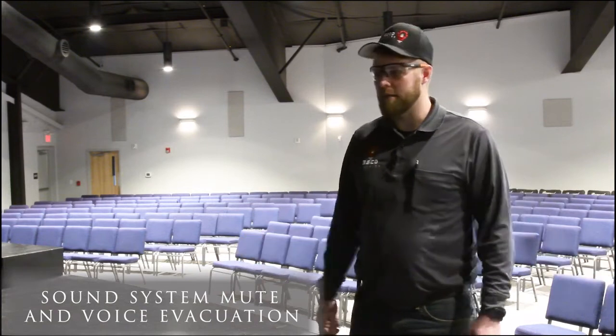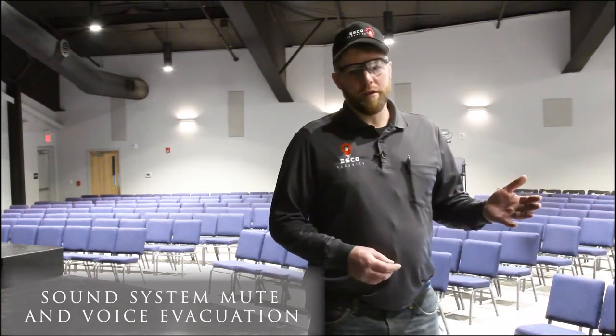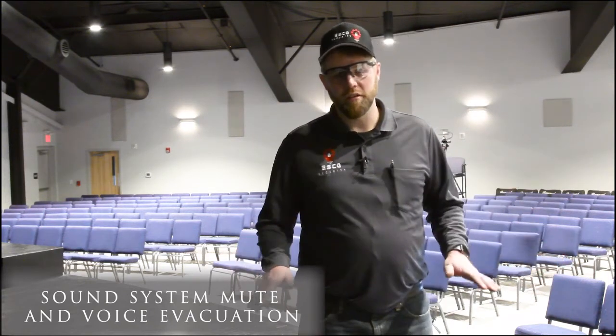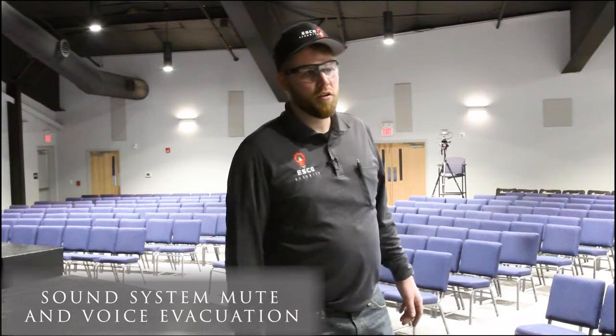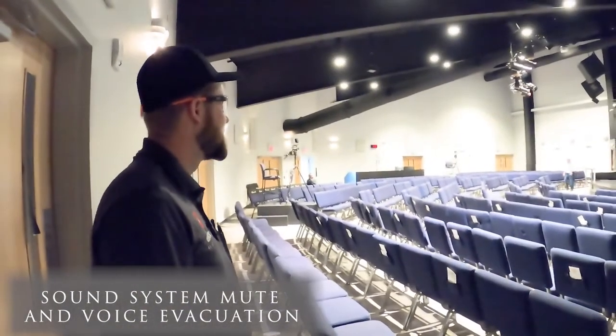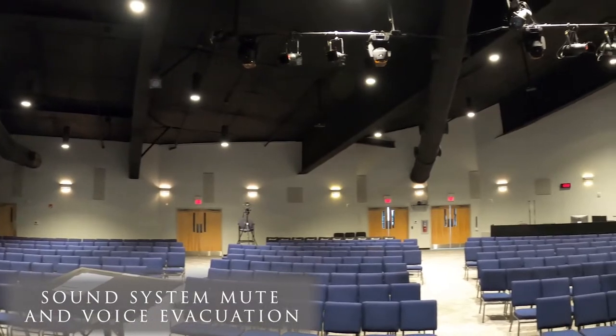Here we are in the main sanctuary of this church and I'm going to show you a feature of the fire alarm system kind of unique to this building. We need to be able to shut down all the audio system when the fire alarm goes off because we need to be 15 dB above ambient. Since we'll never be able to overpower the sound system, we actually have to mute it so that the voice evacuation message can be heard. I'm going to activate the pull station. The fire alarm system took control of our audio system and has muted their speakers so that our voice evacuation speakers can be heard.